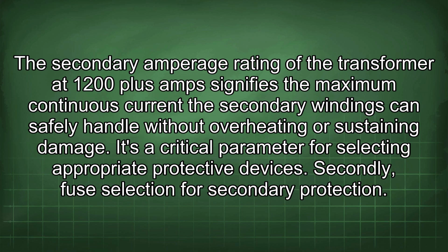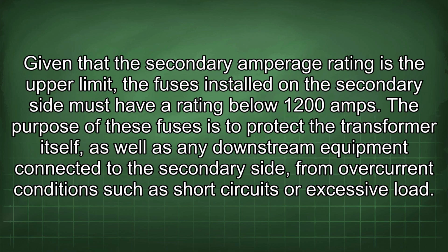Secondly, fuse selection for secondary protection. Given that the secondary amperage rating is the upper limit, the fuses installed on the secondary side must have a rating below 1200 amps. The purpose of these fuses is to protect the transformer itself, as well as any downstream equipment connected to the secondary side, from overcurrent conditions such as short circuits or excessive load.